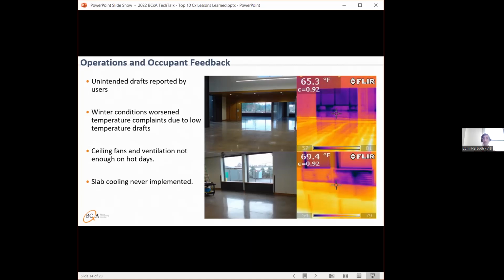And one of the problems there was the slab cooling that was designed was never fully functionally tested and then never implemented. So I don't know if it was just a combination. They had some initial dew point stuff in their programming, but when I went through the commissioning documentation and looked at their functional test records, they were poor. It looked like they did a sampling method on a net zero building, which I definitely recommend staying away from, sampling method on a high performance building.